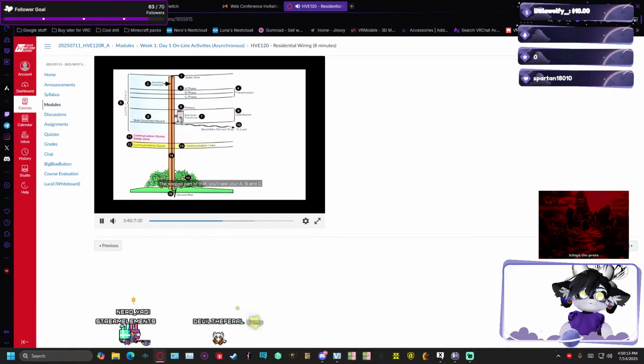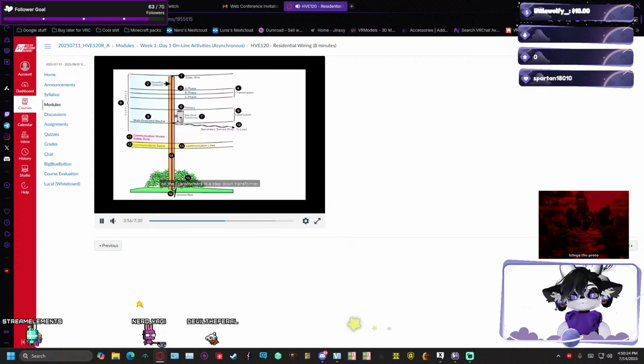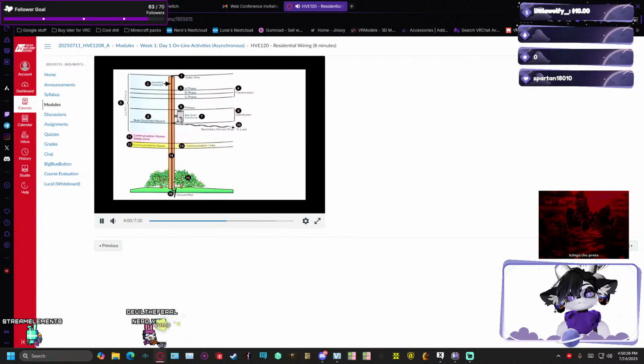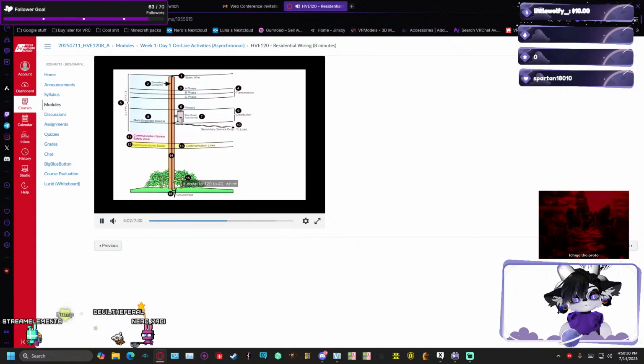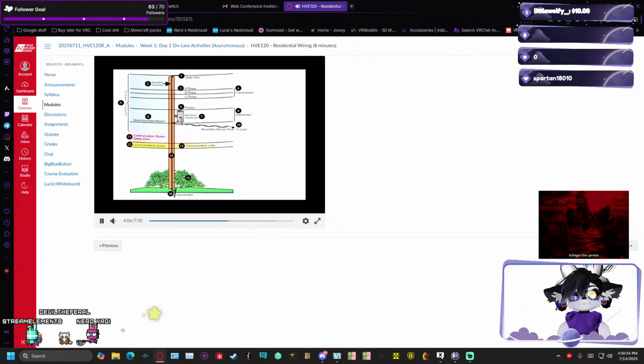The second part of that, you'll see your A, B, and C phases, which is our transmission lines, and they'll tap those to go to our primary for our transformers. On the transformer, it's a step-down transformer, so it's taking that 7,200 volts, stepping it down to 120, 240, which is what we use in our residential applications.